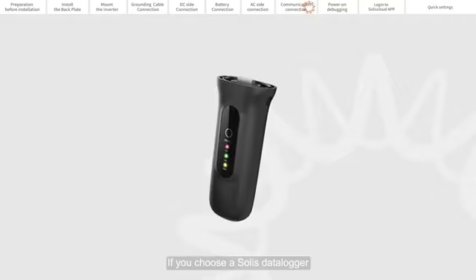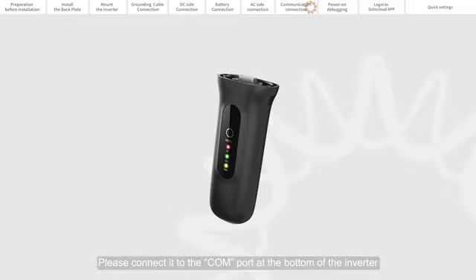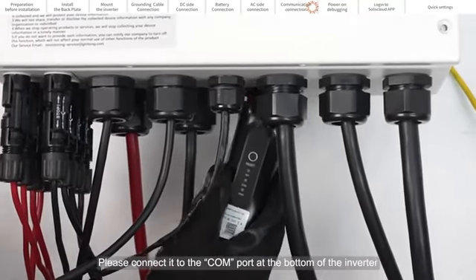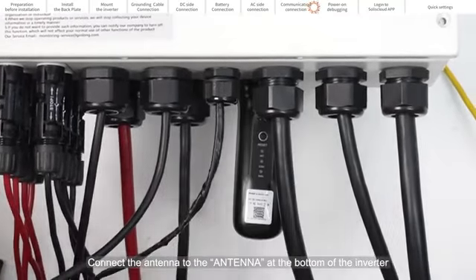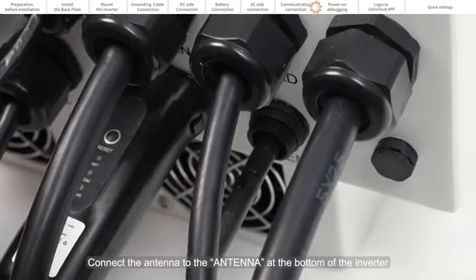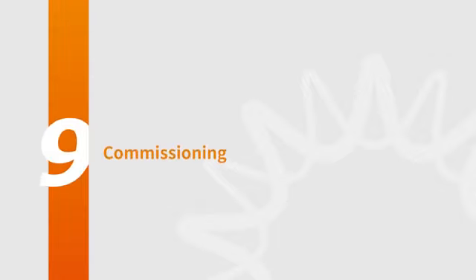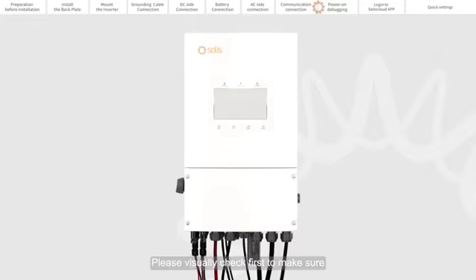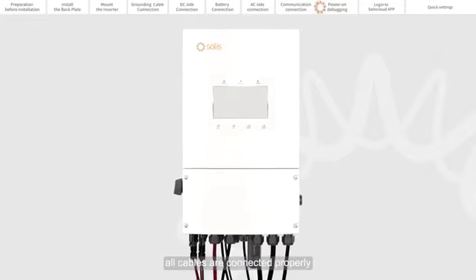If you choose a Solis data logger, please connect it to the COM port at the bottom of the inverter. Connect the antenna to the antenna port at the bottom of the inverter. Part 9. Commissioning. Please visually check first to make sure all cables are connected properly.